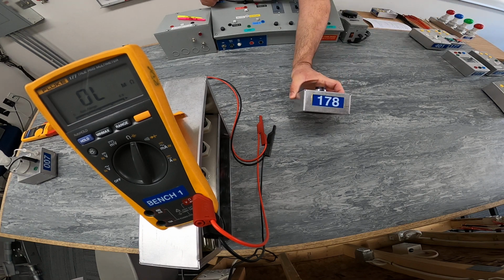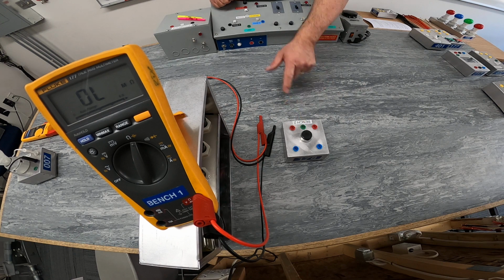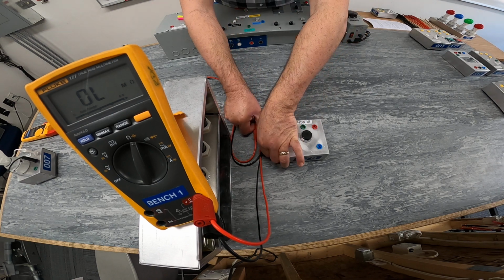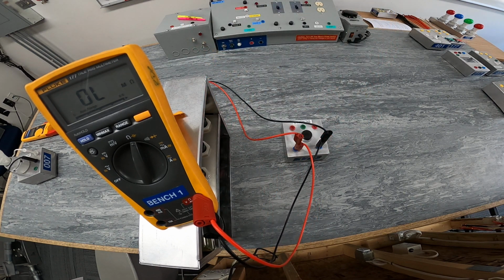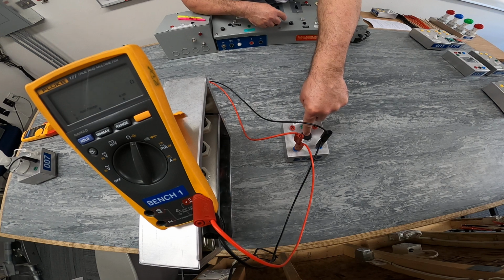This device here is referred to as a 178, and we have a bunch of different connections here. I know that the green connection is a ground connection, so we're not going to be using that. And let's see what happens with just our blue terminals. Okay, so just looking at our blue terminals, we're going to plug our meter into both of those. Without touching our button here, we see that there is no connection. When we depress the button here, push it down, now we have a connection between the 2 blue points.